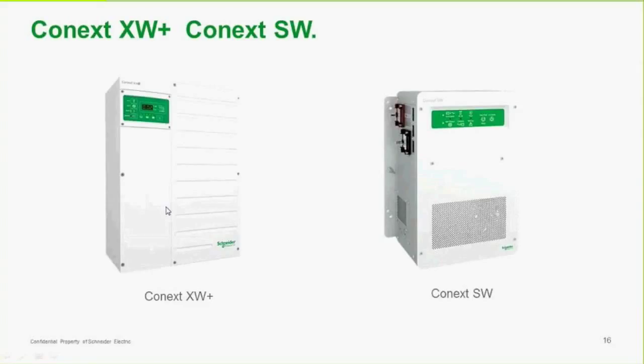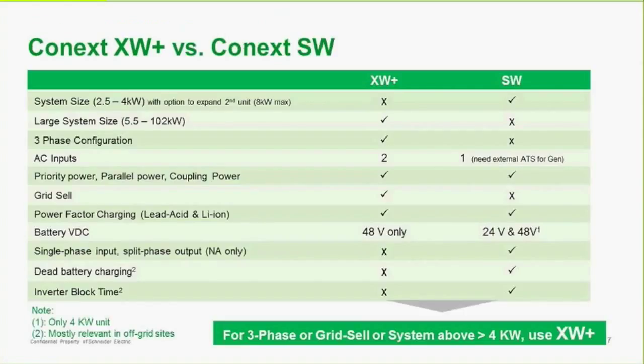There is another inverter in the lineup called the Conext SW. It's a smaller system and doesn't provide all the same features as the XW+, but for small applications it may be more optimal. Comparing the two: the XW+ is not made for smaller applications, whereas the SW has a maximum size of 4 kilowatts. You can put two SWs together for a total of 8 kilowatt supply. The XW+ can be stacked, and in a three-phase system you can get up to 102 kilowatts.